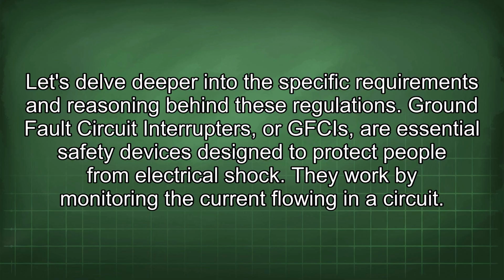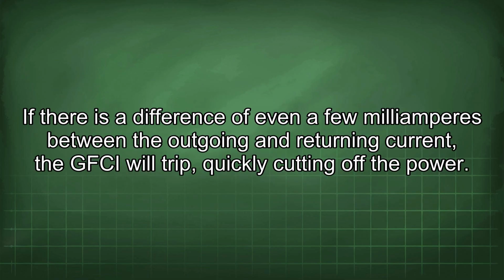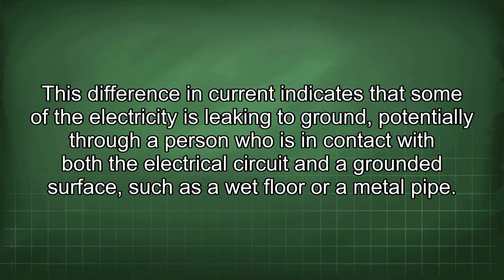Ground fault circuit interrupters, or GFCIs, are essential safety devices designed to protect people from electrical shock. They work by monitoring the current flowing in a circuit. If there is a difference of even a few milliamperes between the outgoing and returning current, the GFCI will trip, quickly cutting off the power. This difference in current indicates that some of the electricity is leaking to ground, potentially through a person who is in contact with both the electrical circuit and a grounded surface, such as a wet floor or a metal pipe.